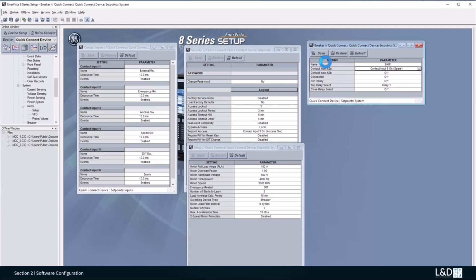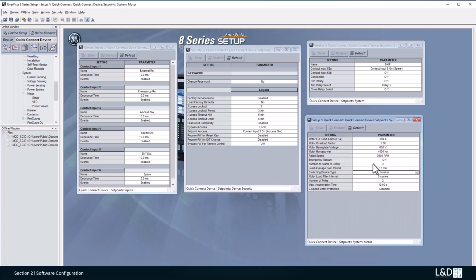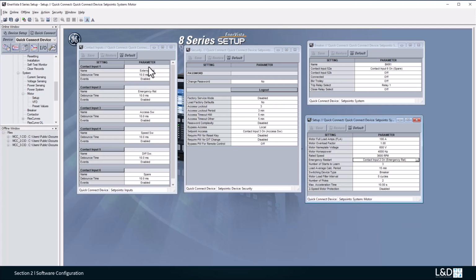And another example is the emergency restart. We can do this setting under the same setup of this motor, emergency restart. We can choose here and set it to contact input 2. So that's all the digital input settings in the 859. They're called the contact inputs, and they still use the same default names as in the 369.